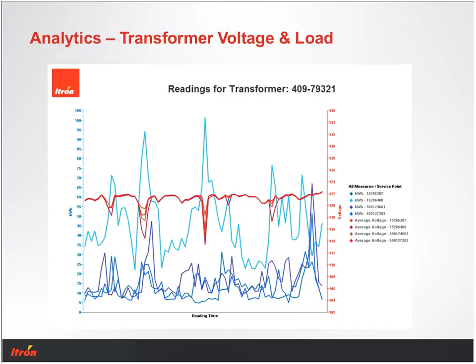This probably is something more like a small commercial one with some residential loads, and so here I can actually mitigate the circumstance which might prevent me from lowering the voltage on this particular feeder. So this is what we're really after, to determine that potential and to be able to mitigate the possibilities that are limiting us with equipment and installation issues.